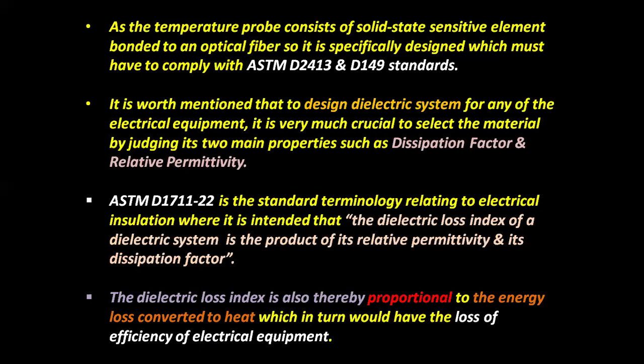ASTM D1711-22 is the standard terminology relating to electrical insulation, where it is stated that the dielectric loss index of a dielectric system is the product of its relative permittivity and its dissipation factor. The dielectric loss index is thereby proportional to the energy loss converted to heat, which in turn causes a loss of efficiency of electrical equipment.